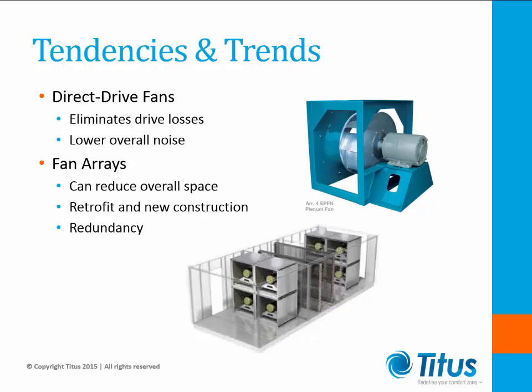1, 2, and 4 fan systems provide overwhelming advantages over stacked multi-fan arrays. The need for full fan redundancy should be challenged sometimes. Systems should be designed around 1 or 2 fans to maintain peak efficiency, and housed centrifugal fans should be considered when unit length is available.